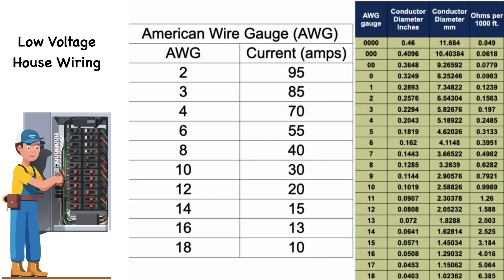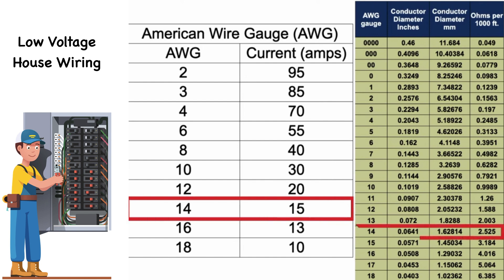These two charts describe the characteristics and capabilities of the various wire gauges of copper wire. The chart on the left is the current-carrying capacity of the various copper conductors. For example, for a load that draws 15 amps, number 14 AWG wire is required. The chart on the right, along with describing the diameter, indicates the resistance of the wire in ohms per 1000 feet, which is significant for long runs of cables.